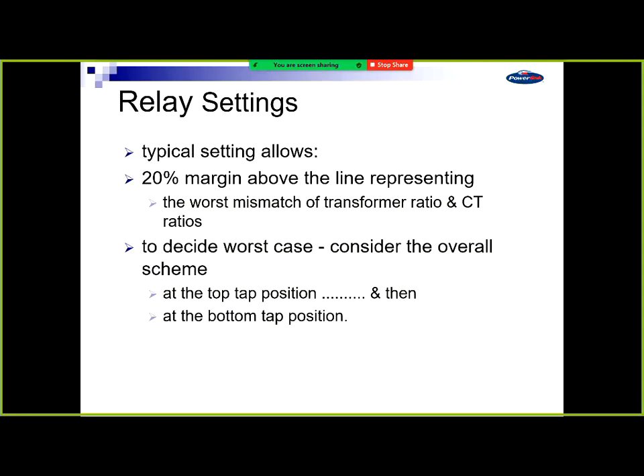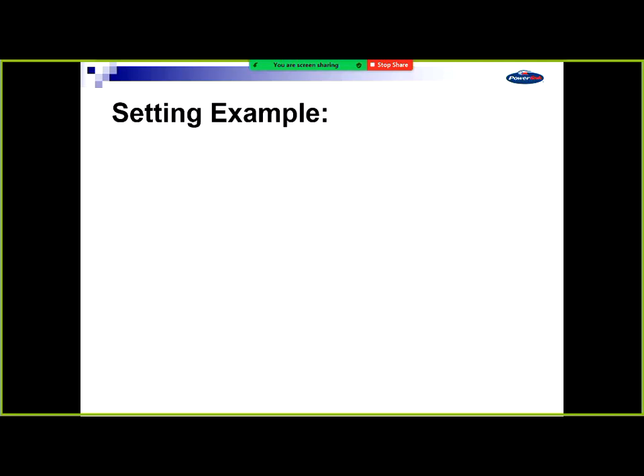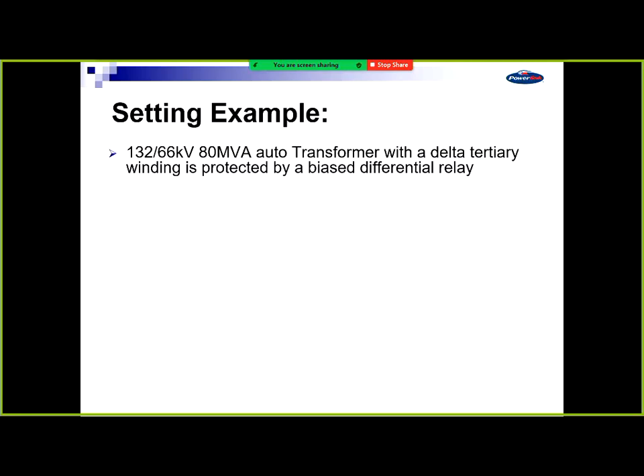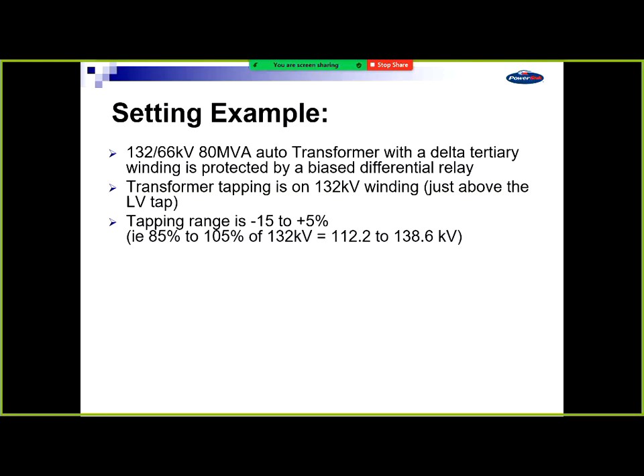Not too conservative, not overly aggressive that you trip incorrectly. One thing you don't want to do is trip incorrectly. So here's an example. This is an 80 MVA transformer with a delta tertiary, which would be 11 kV, protected by a bias diff, and on the windings, the tappings range from -15 to +5, so we go from 112.2 to 138.6 kV. The CT ratios chosen are 600 and 1200 to 1.